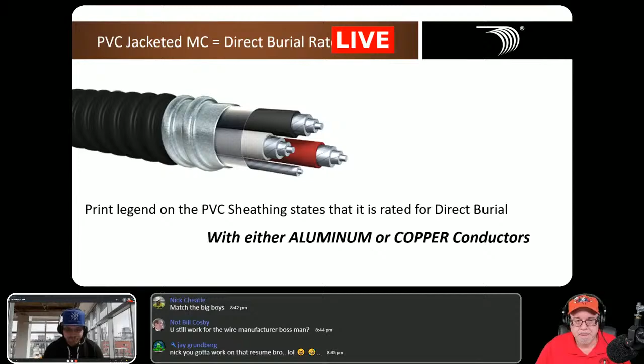It is a lot lighter. And obviously it has to be a little larger to carry the same amount of current as copper would. But since pretty much all aluminum today is compact aluminum, it has no interstices inside of it, those little voids between strands, so it has a smaller footprint. Copper is still going to be smaller at the same ampacity value, but because all the aluminum is compact today, it's really not a huge difference like it used to be. It used to be when it was concentric, with all those round strands and little voids that take up space. Now everybody pretty much uses compact, so it doesn't have the same issue.